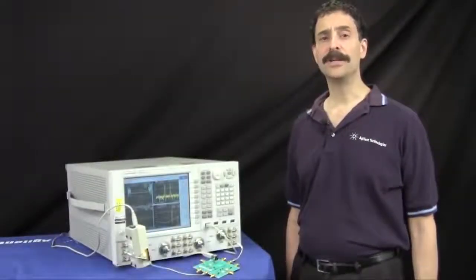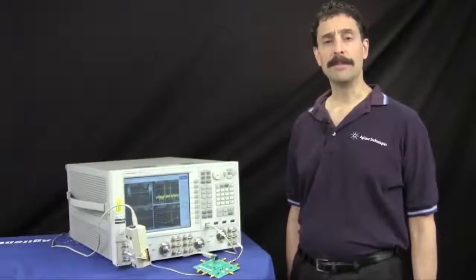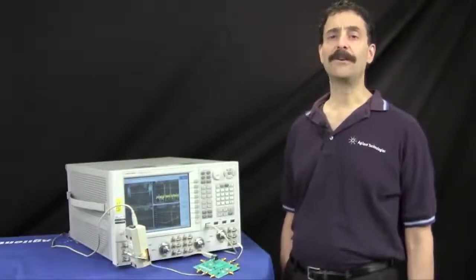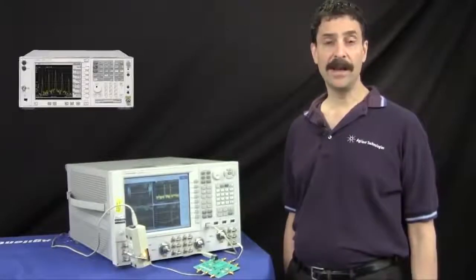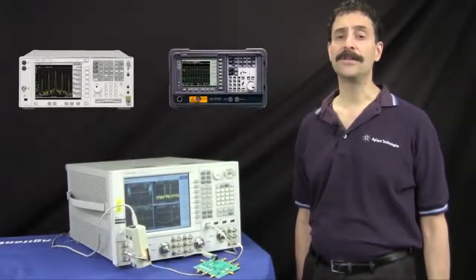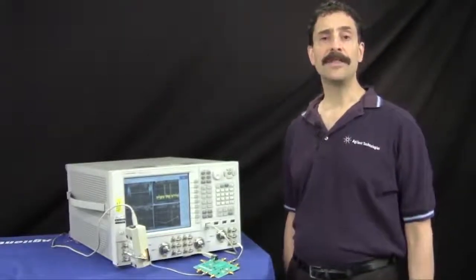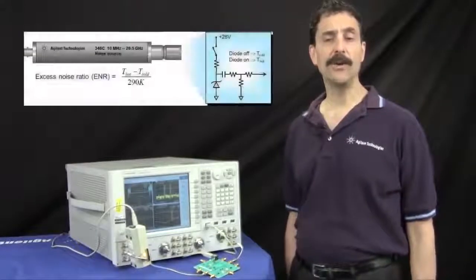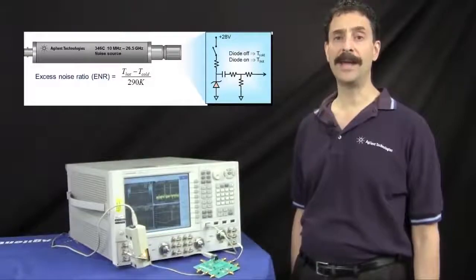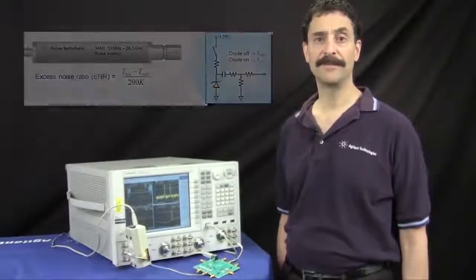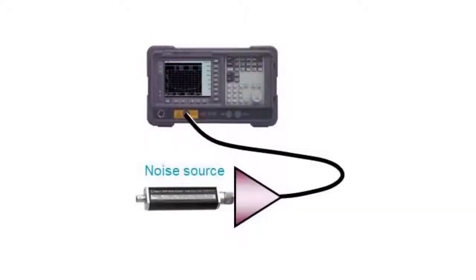How is noise figure measured? The most common measurement approach is called the Y-factor method. This method is used with Agilent's spectrum analyzers and noise figure analyzers. The Y-factor method uses a calibrated noise source, which is assumed to present a perfect 50 ohm match to the DUT. Y-factor measurements provide good results for most connectorized devices, especially when using low ENR noise sources.